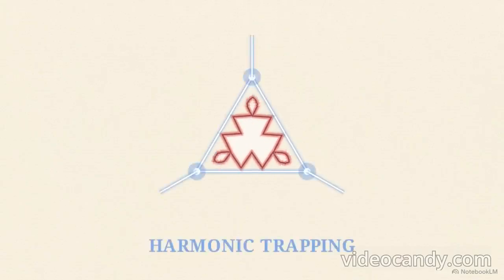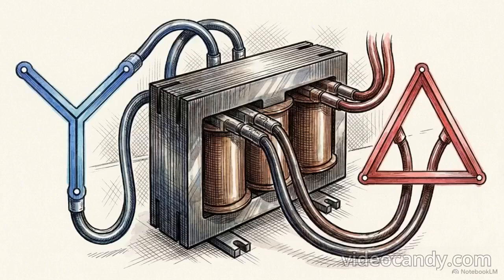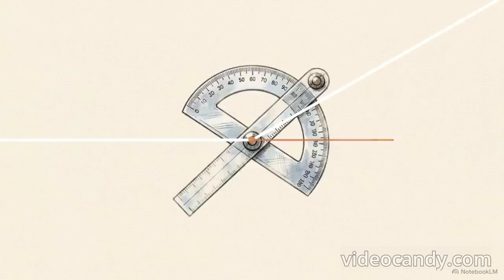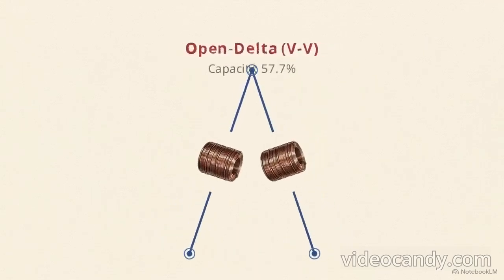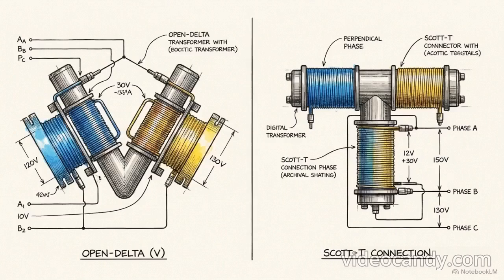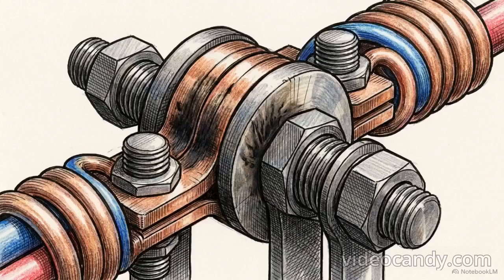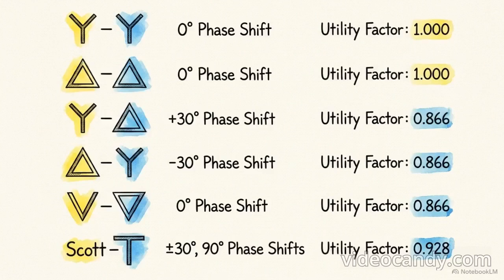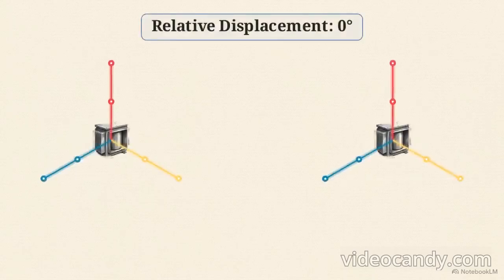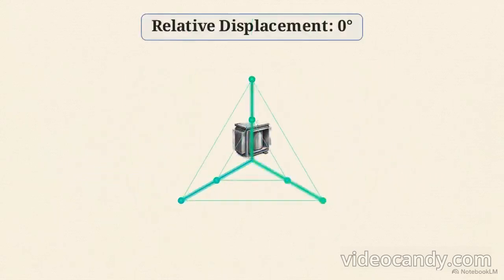When you look at the towering high-voltage lines stretching across the landscape, you are actually looking at a physical expression of vector geometry. We rely on the symmetrical star connections to save on insulation costs, and we deploy closed delta configurations to trap harmonics and stabilize the current. To transfer power across varying voltage levels, we cross those topologies with Y-delta transformers, deliberately accepting the permanent 30-degree phase shifts they inject into the grid. And when symmetry breaks or dimensions need to shift, we lean on the asymmetrical open delta and Scott-T architectures, trading physical hardware efficiency for operational continuity.